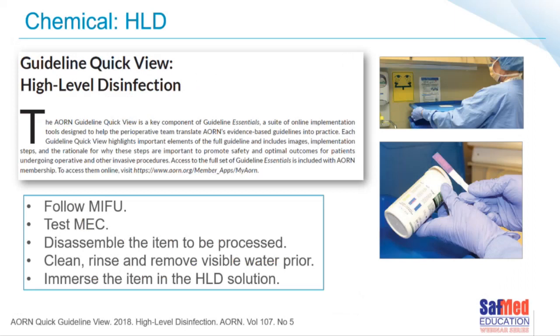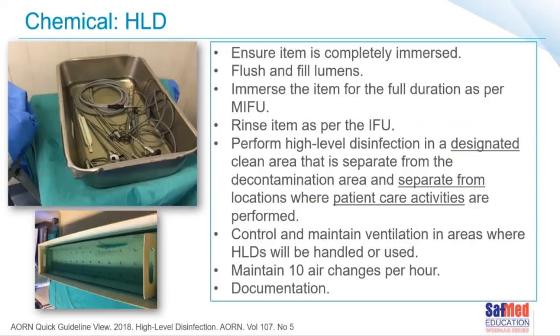The AORN guidelines, a quick review of the guideline on high-level disinfection and management of high-level disinfection. And I know you know this, you really and truly do this every day. And simple but important reminders, of course, to follow the manufacturer's instructions for use, to test the minimum effective concentration, to disassemble the item to be processed, to clean, rinse, and remove visible water prior to actually immersing, and of course then eventually immersing in the high-level disinfectant solution.